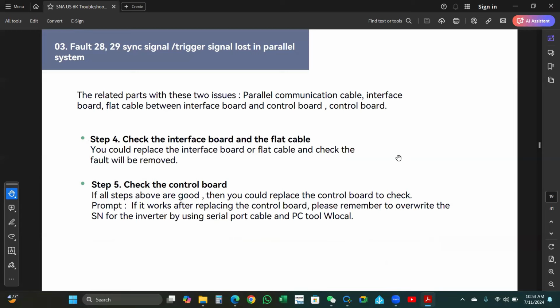Step 4, check the interface board and the flat cable. You could either replace the interface board or the flat cable and check if the fault is removed. Step 5, check the control board. If all steps above are good, then you could replace the control board to check. Prompt: if it works after replacing the control board, please remember to overwrite the SN, the serial number for the inverter, by using the serial port cable and PC tool.